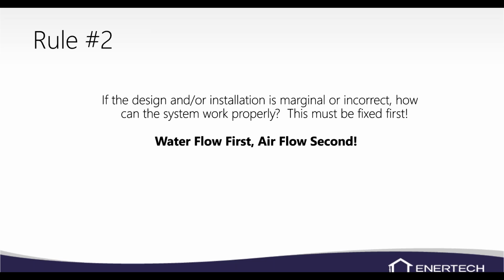We always start on water flow first, airflow second. It's easier, again, to know if you have airflow. If you've got a blower bearing unit, you can hear the blower, you're standing right there. So water flow first. So obviously we'll start up the system, and we need pressure temperature ports on the water lines. Whenever you're installing a unit, whether it's a water-to-water unit or a forced air unit, make sure we're installing pressure temperature ports. It's hard for tech support to know what the water flow is without pressure drop.